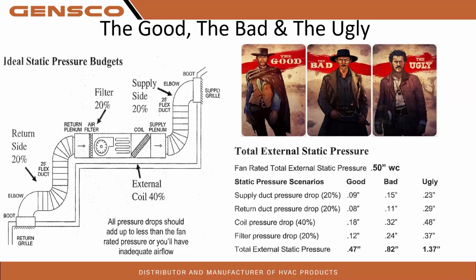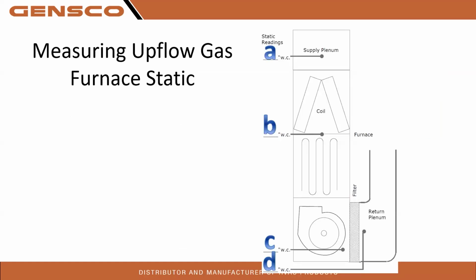On fieldtechhelp.com, there's a great one, Obituary of a Compressor. It's a 4-hour refrigeration tutorial class showing you the effects of airflow on the indoor coil, how it's going to kill that compressor, and how it's going to affect that TXV or EEV operation because of poor airflow. So yeah, I definitely recommend watching that one. These are great slides and we can send them out. Again, if anybody wants this, go ahead and put it in chat. We have forms for you to share with your guys in the field, or if you're somebody in the field who wants these forms, they are great to fill out, because once you fill out enough data on these forms, you'll start seeing the issues present themselves as you're filling in the data.